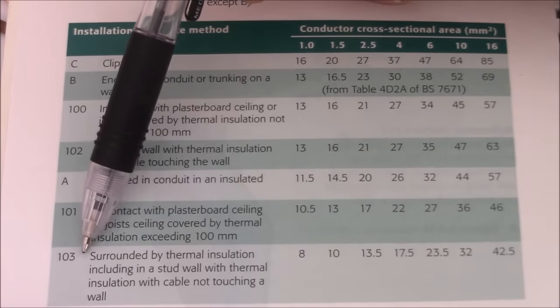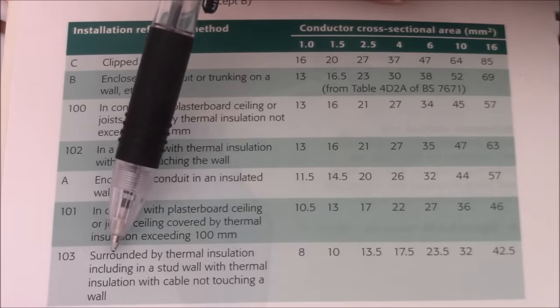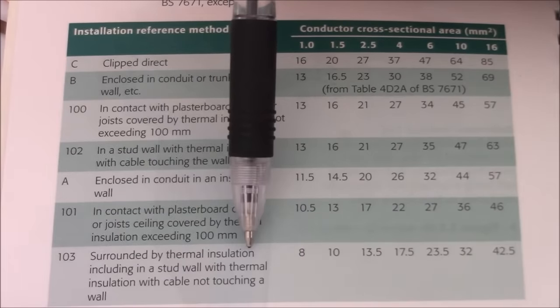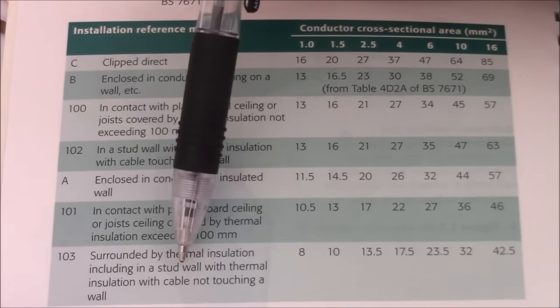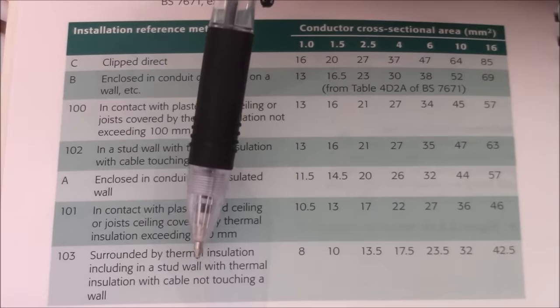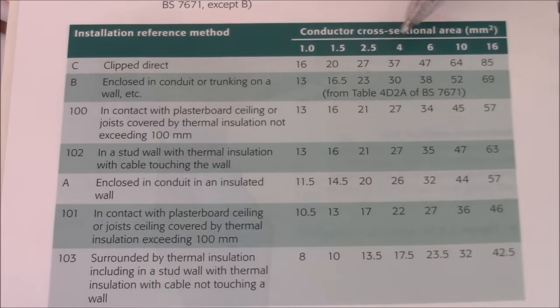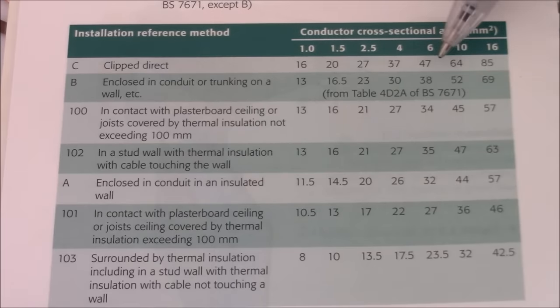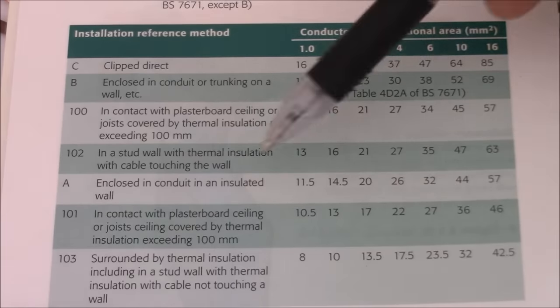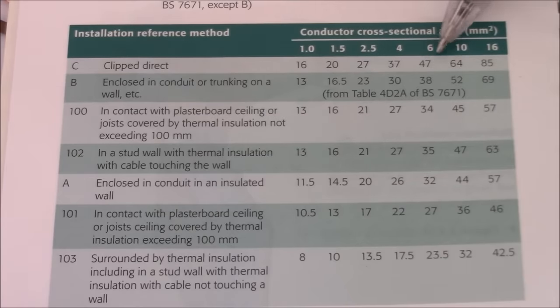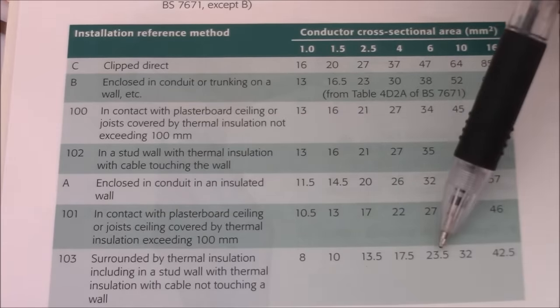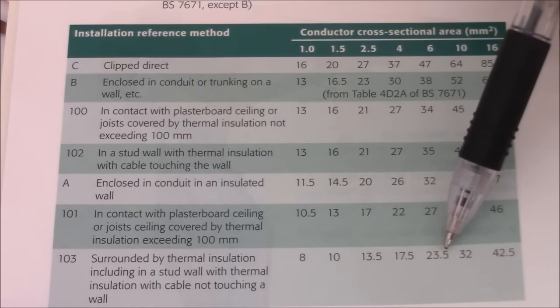So let's see the reference method 103. This is surrounded by thermal insulation completely, so basically from every side. So now look at the cable let's say 6 mm. When you clip direct to the wall it's 47 amps the rating. But when you wrap it, when you put it into insulation and wrap it completely, the rating falls down to 23.5 amps.